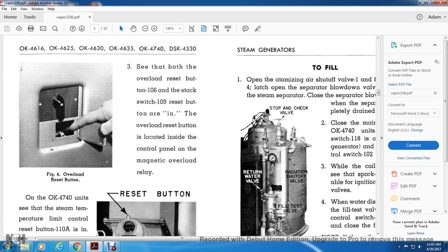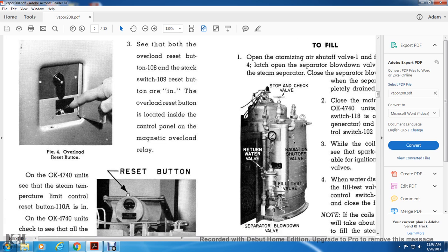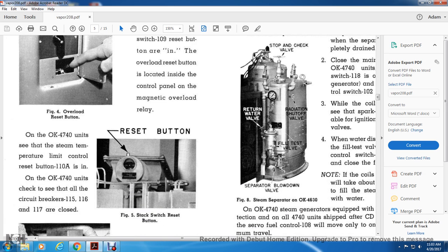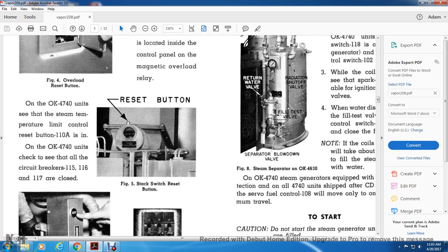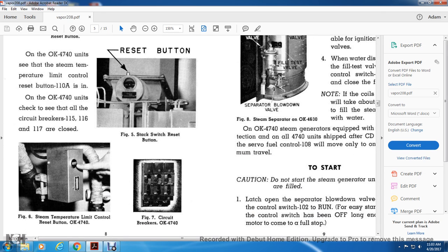Three. See that both the overload reset button 106 and the stack switch 109 are in. The overload reset button is located inside the control panel over the magnetic overload relay. Figure 4 shows the overload reset button. On the OK4740 unit, see that the steam temperature limit control reset button 110A is in. On the OK4740 units, check that all the circuit breakers 115, 116, and 117 are closed. Figure 5 shows the stack switch reset button. Figure 6 shows the steam temperature limit control reset button. Figure 7 shows the circuit breakers on the OK4740 model.